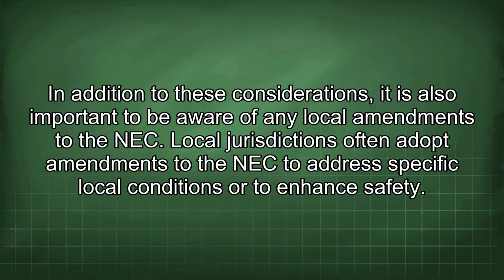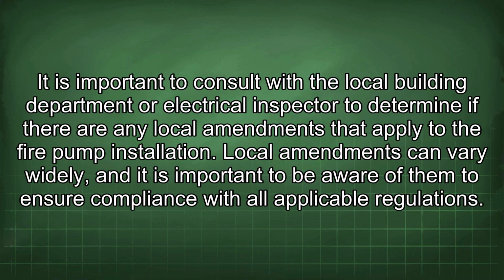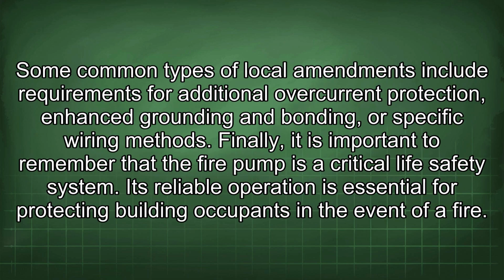Local jurisdictions often adopt amendments to the NEC to address specific local conditions or to enhance safety. It is important to consult with the local building department or electrical inspector to determine if there are any local amendments that apply to the fire pump installation. Local amendments can vary widely, and it is important to be aware of them to ensure compliance with all applicable regulations. Some common types of local amendments include requirements for additional overcurrent protection, enhanced grounding and bonding, or specific wiring methods.